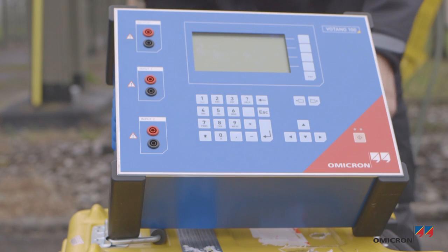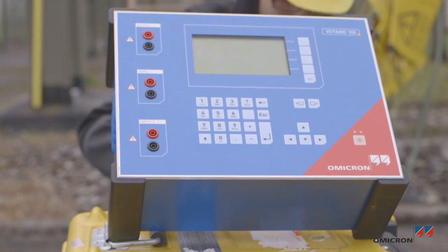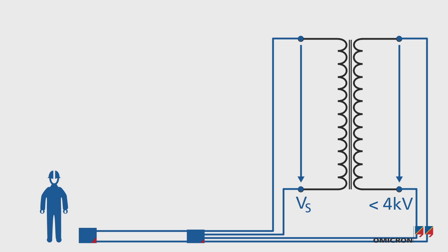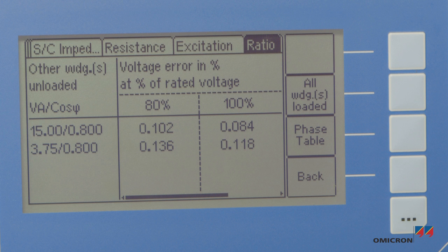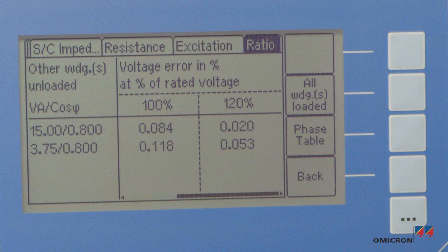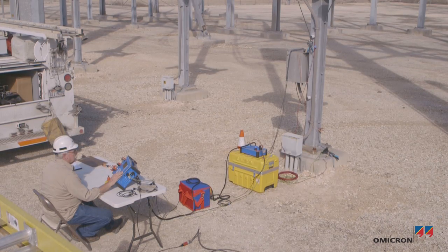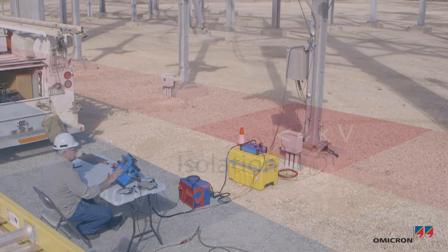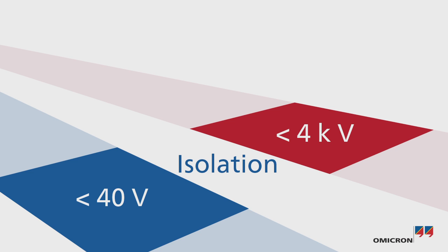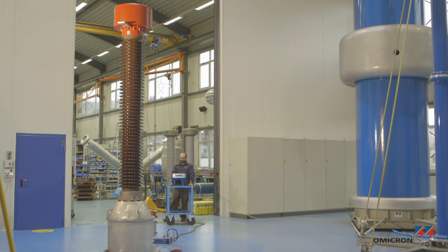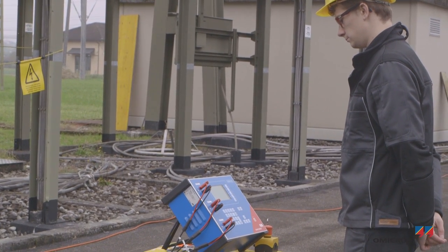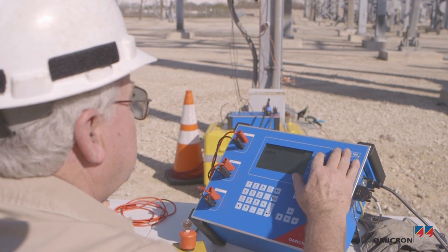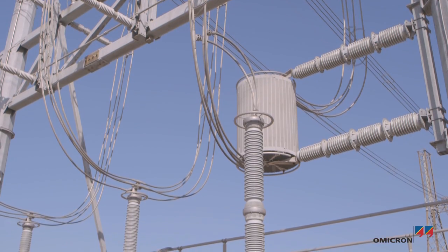Omicron's Votano 100 uses a modeling approach. The modeling approach allows the accuracy to be verified by determining the elements of the voltage transformer's equivalent circuit, and subsequently calculating the error. This approach increases the safety level of the personnel and reduces the amount of effort required in factories, labs, and on site. Votano 100 has made testing voltage transformers economically feasible for many operators.